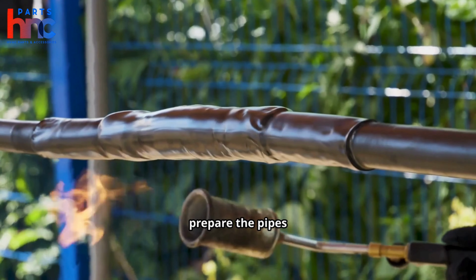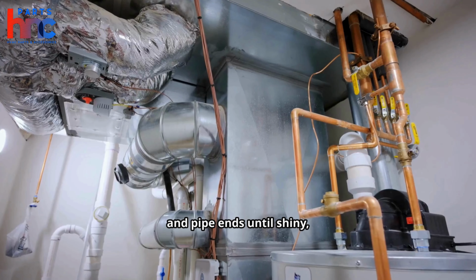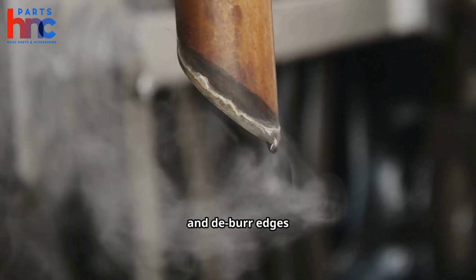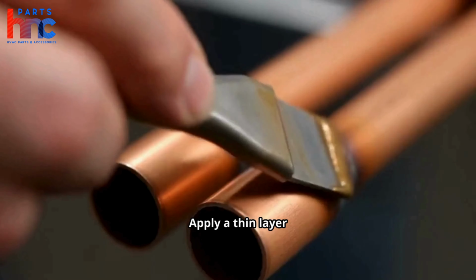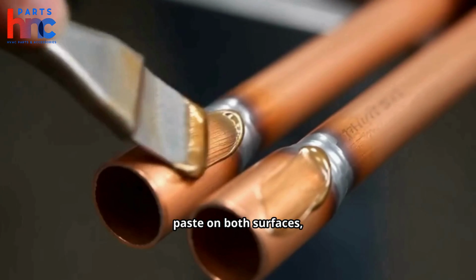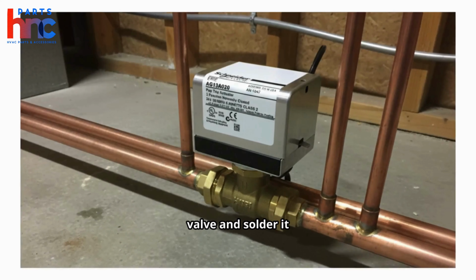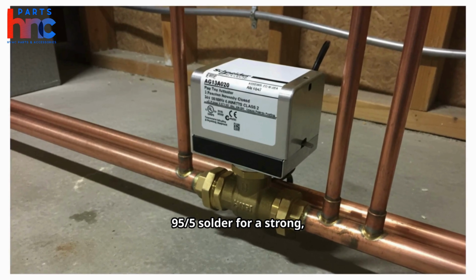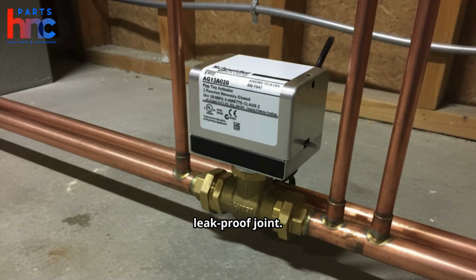Next, prepare the pipes for soldering: clean the fittings and pipe ends until shiny, and deburr edges to prevent leaks. Apply a thin layer of flux or soldering paste on both surfaces. Then position the valve and solder it using MAP gas and 95/5 solder for a strong, leak-proof joint.